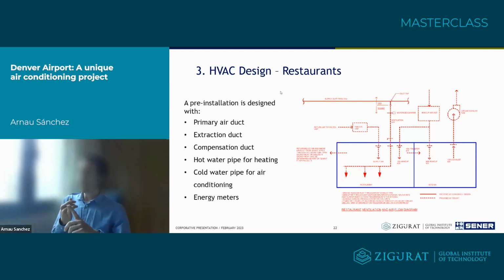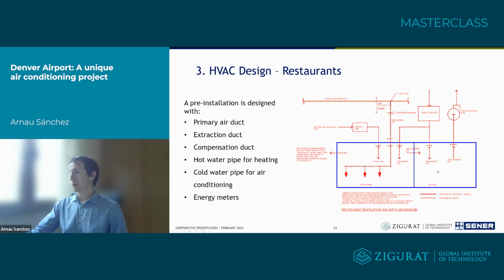So we provide primary air ducts, we provide an exhaust duct for the kitchen, we provide a compensation duct for the makeup air in the kitchen. We provide as well hot water and cold water for the air conditioning and heating, and obviously there are energy meters so the airport can measure the energy each tenant is consuming, and then they will pay for it.